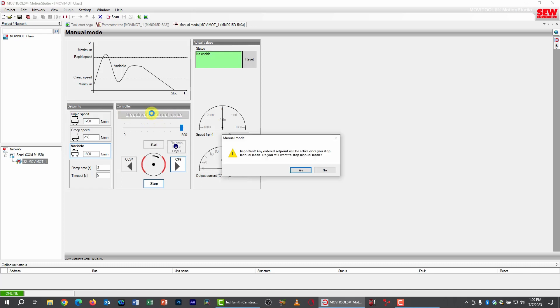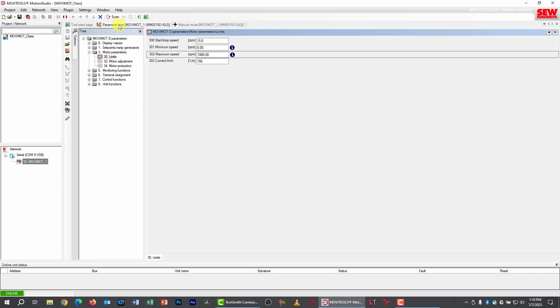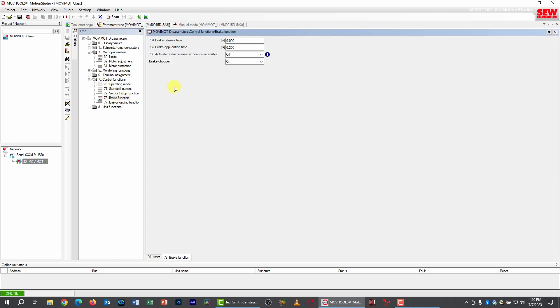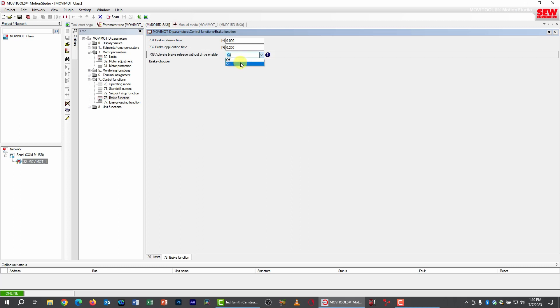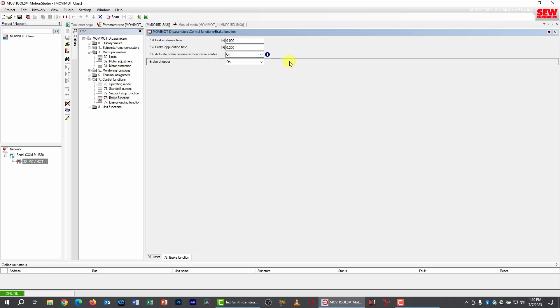Now I need to deactivate manual mode first and go back to my parameter tree, and I'm going to go to parameter group 7 control functions and pick subgroup 3 brake function. And here is the parameter of interest, 738, activate brake release without drive enable. It defaults to off, which is the way we normally want the brake to behave. But notice it's got that blue eye because that indicates there's a dip switch that controls it as well. Now we've disabled all the dip switches, so we're going to control this by parameter. So I'm going to turn this on, and this enables me now to release the brake without enabling the motor. There are reasons you might want to do this. In some applications, maybe you need to move something manually. You don't want to use the motor. You want to move it physically just by releasing the brake and maybe turning it or shoving it.